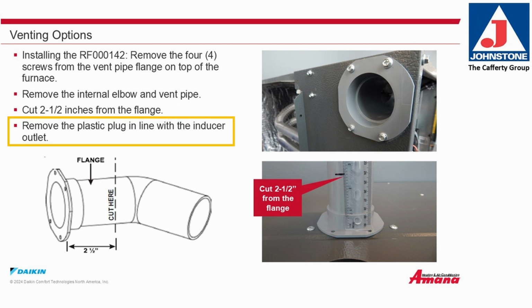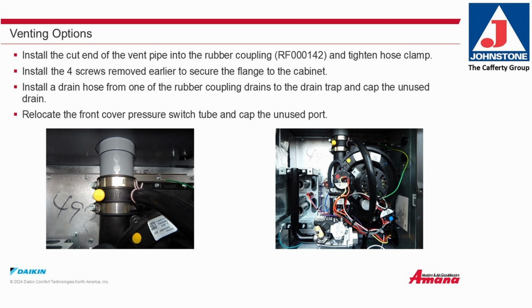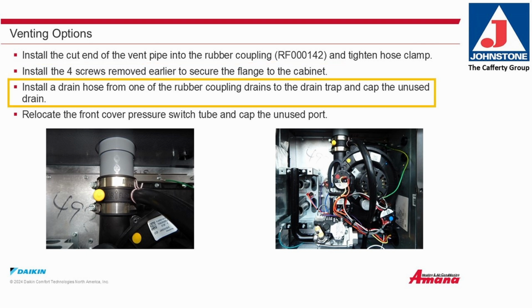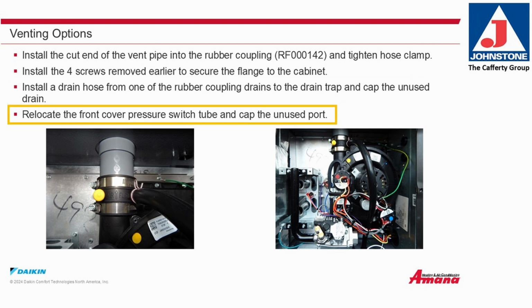Remove the plastic plug from the side of the furnace in line with the inducer outlet. Install the cut end of the vent pipe into the rubber coupling and tighten the hose clamp. Install the 4 screws you removed earlier to secure the flange to the cabinet. Install a drain hose from one of the rubber coupling drains to the drain trap and cap the unused drain. Relocate the front cover pressure switch tube and cap the unused port.